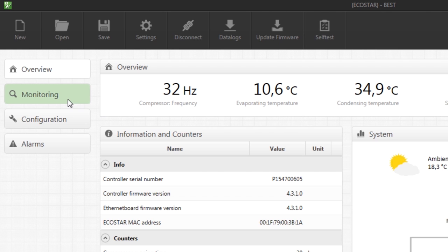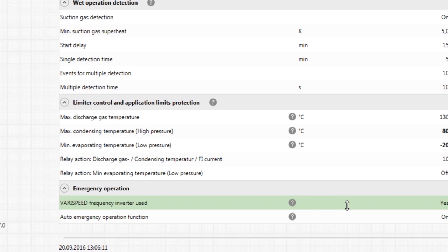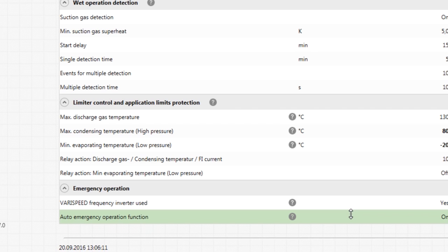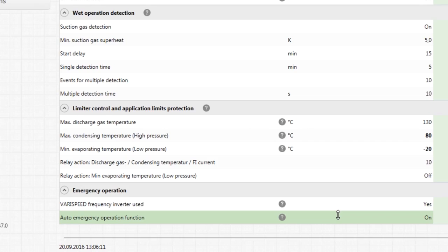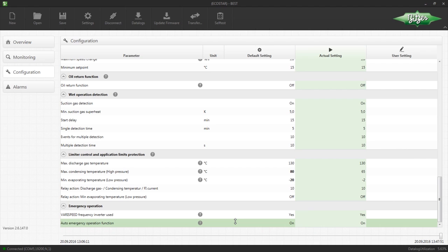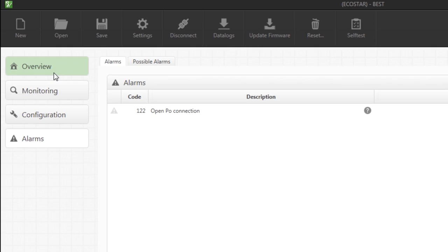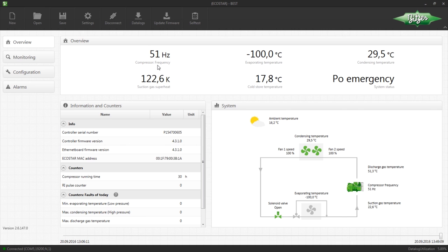All the operating parameters measured are displayed under monitoring. The special emergency service function ensures uninterrupted cooling in emergency situations. The compressor and fans run at a fixed speed to ensure a continued supply of cooling. This process will now be simulated. The alarm appears in the alarm menu item. The overview menu shows that the compressor is running at a constant speed.